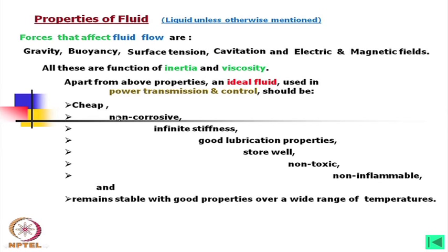The fluid should be non-corrosive. Most components are ferrous material, and we should look into the fact that the oil should not be corrosive — no rust should come over the ferrous components. Infinite stiffness means we wish the fluid should be incompressible and stiff in such a way that it behaves like a solid material while transmitting force.